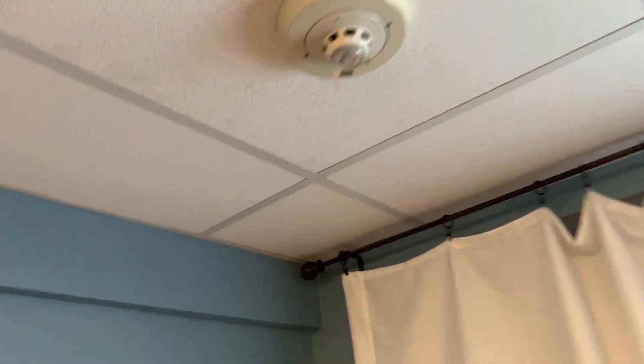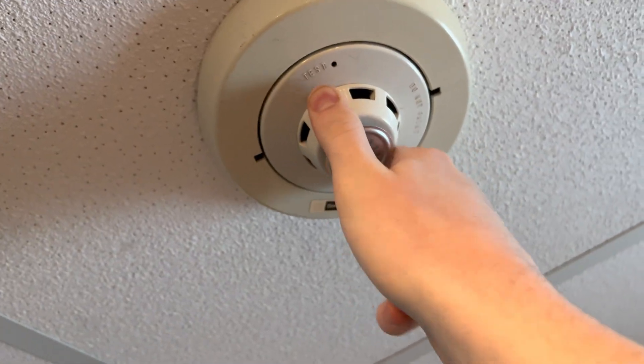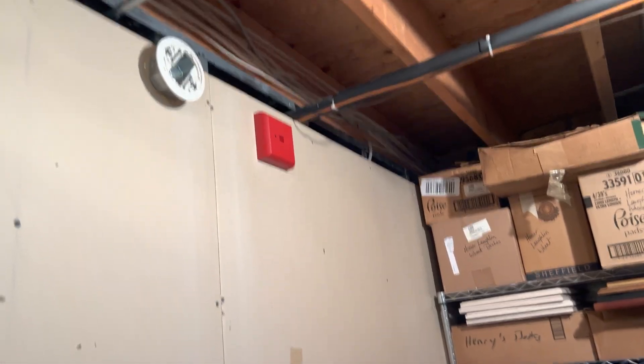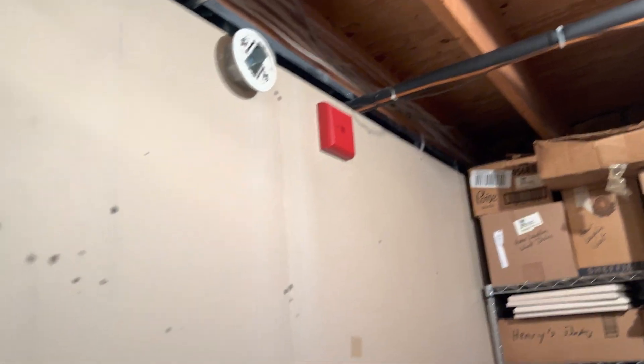If we come over here, we have a Simplex four-wire smoke detector base with a Simplex smoke and heat detector. Coming to here, we have a Mircom pull station with the Faraday 2881, which is what the Siemens UMMT was before Siemens owned Faraday. That is set on continuous horn.